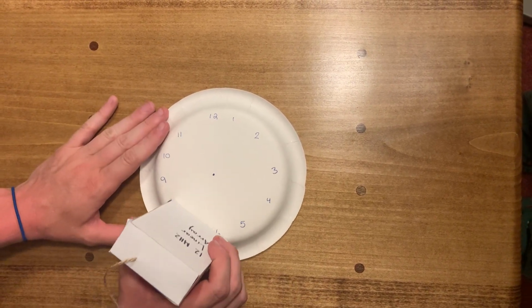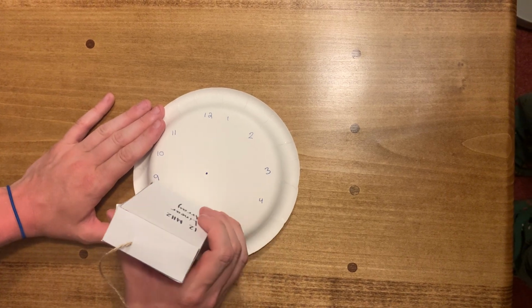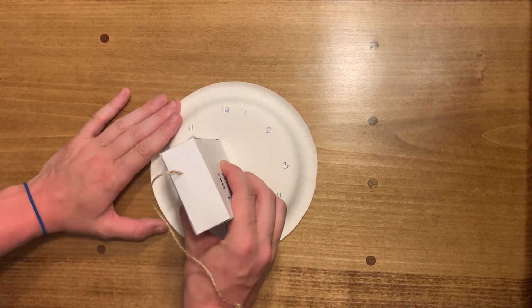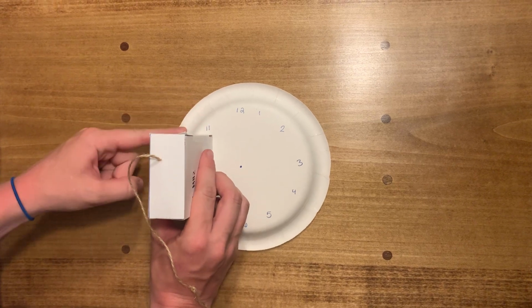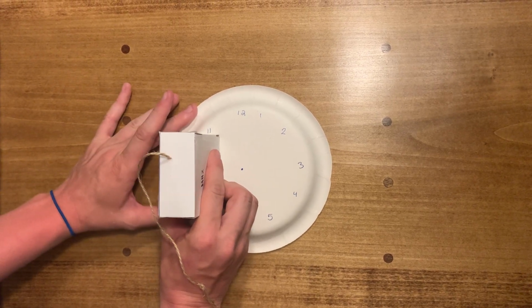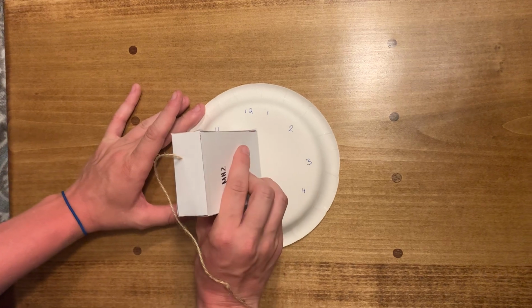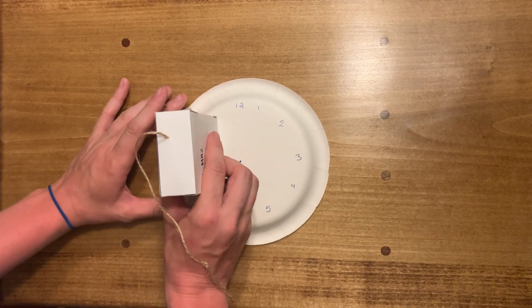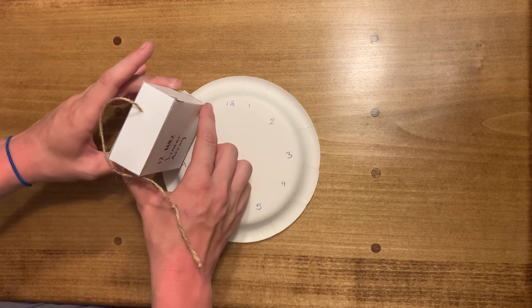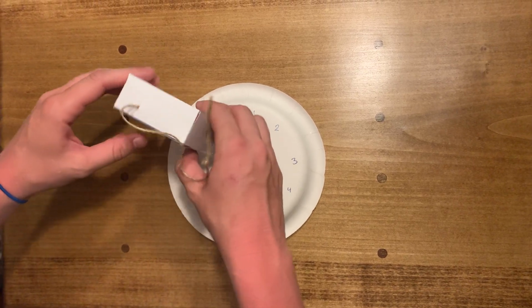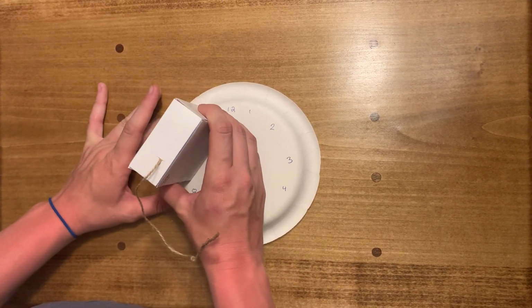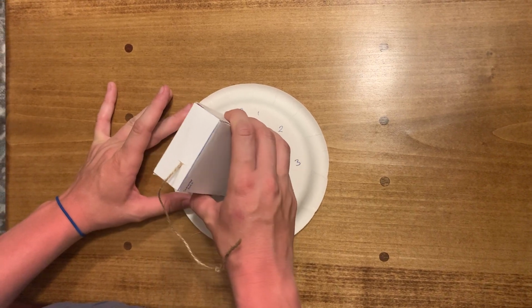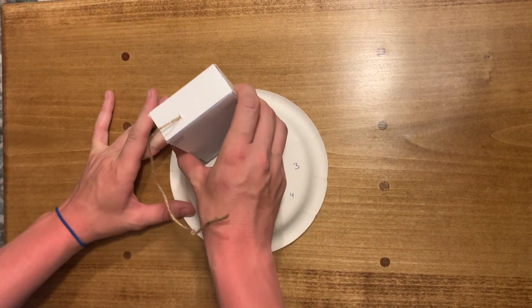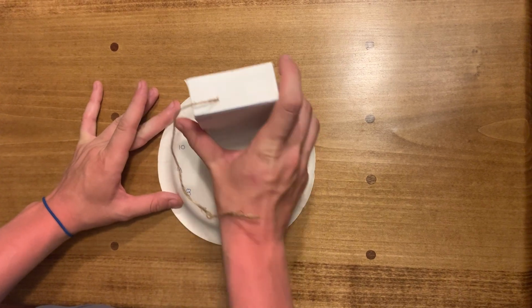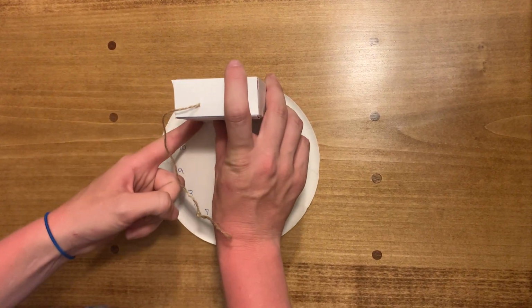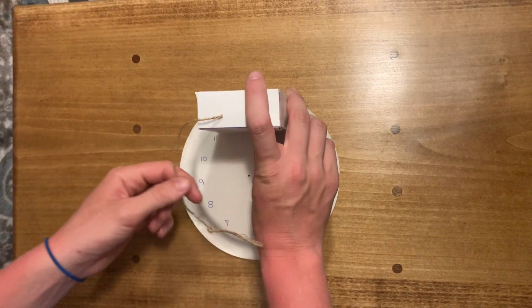7 o'clock, angle. 8 o'clock, angle. 9 o'clock, the notch is facing towards the patient's head. Scan and angle under. Now when we get to 10 o'clock, just as we did at 4, the notch will be facing towards the patient's left. So we're going to rotate counterclockwise again and continue scanning. Angle under the nipple. 11 o'clock, angle under the nipple. And now we're back to 12, and our transducer notch is towards the patient's right.